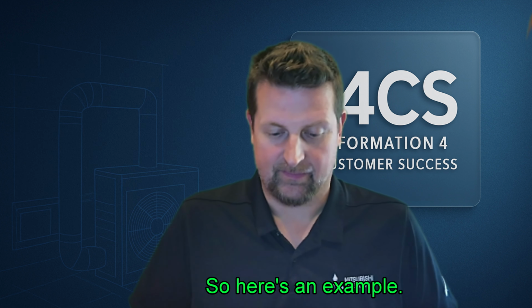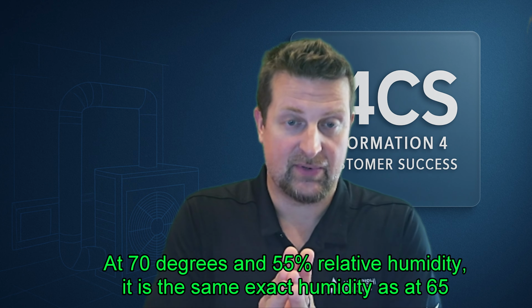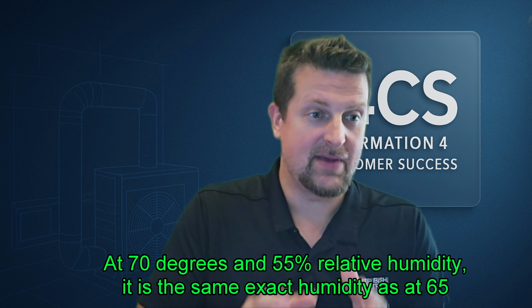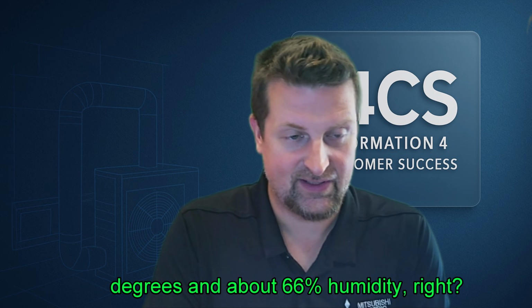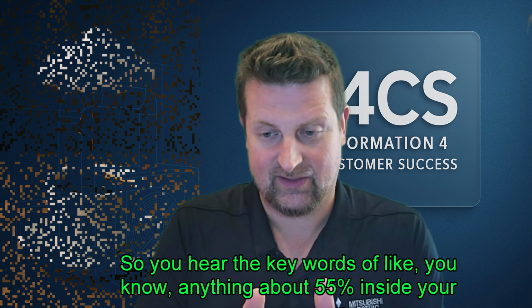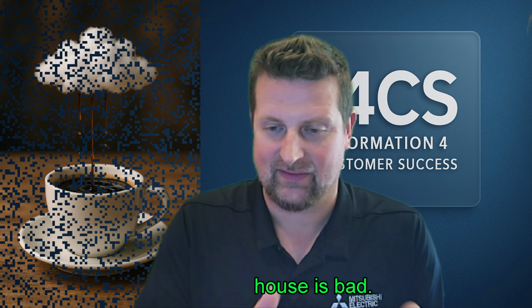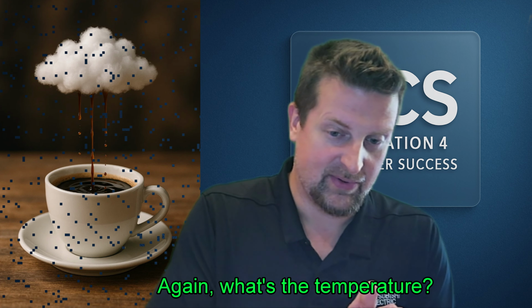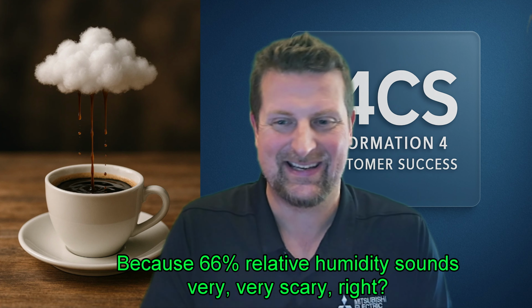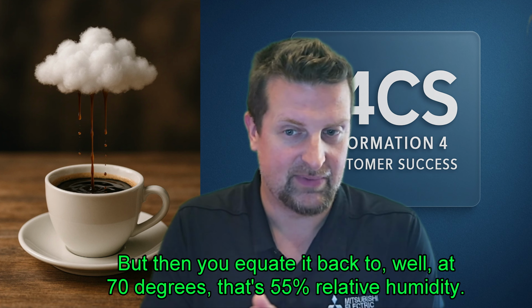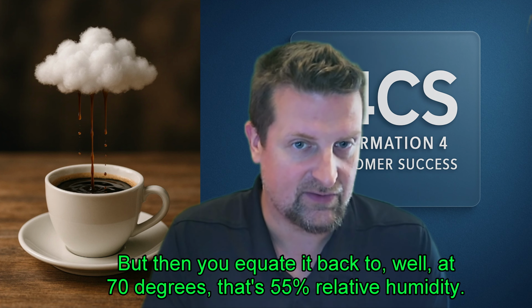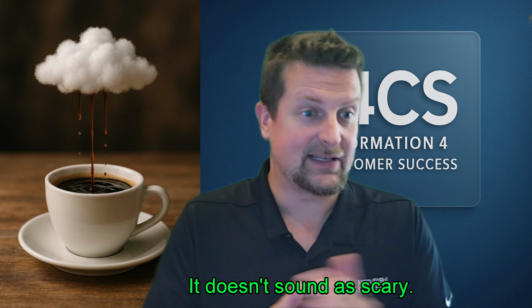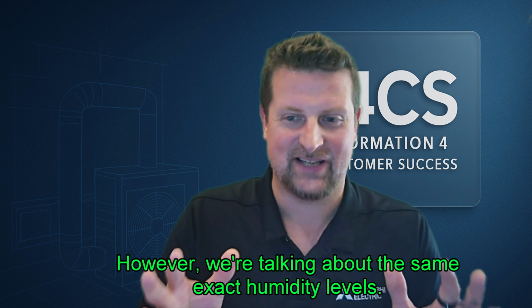So here's an example. At 70 degrees and 55% relative humidity, it is the same exact humidity as at 65 degrees and about 66% humidity, right? So you hear the keywords of anything above 55% inside your house is bad. Again, what's the temperature? Because 66% relative humidity sounds very, very scary, right? But then you equate it back to, at 70 degrees, that's 55% relative humidity. It doesn't sound as scary. However, we're talking about the same exact humidity levels.